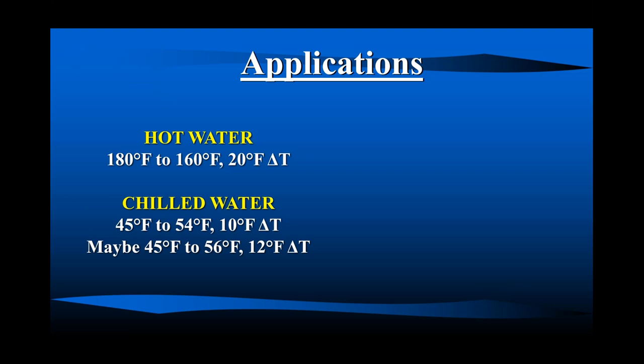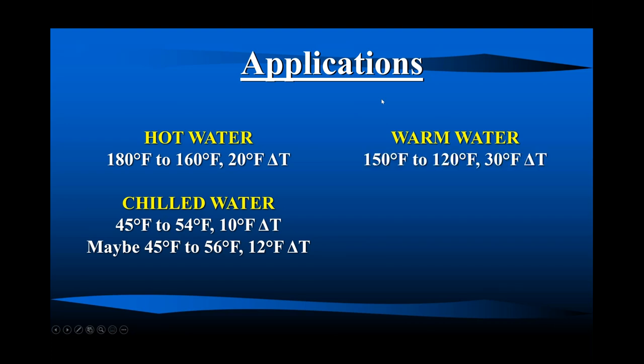But all these fabulous systems out there have different temperatures. So most of our applications now are going to be for warm water, which probably is a 150 to 120 system, 30 degree delta T, very nice. Nice reduction of pumping power, and 150 to 120, that 120 is a great number, especially if we're using a condensing boiler, right? That makes those boilers condense nicely.